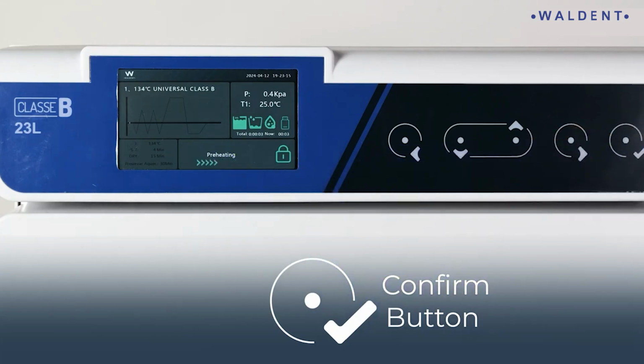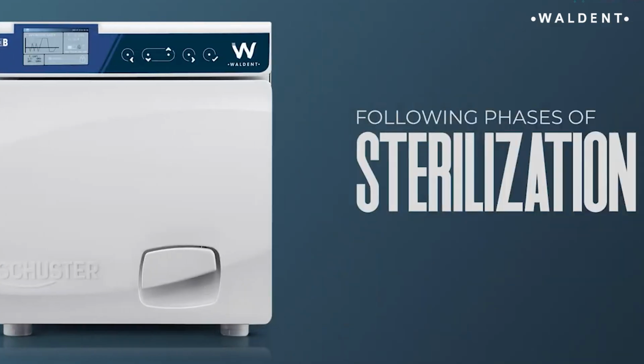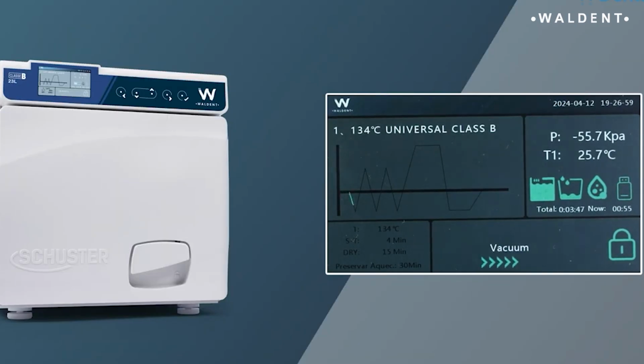Similarly, different cycles have different sterilization times. There are following phases of sterilization: preheating followed by vacuum, then heating, second time vacuum, again heating, third final time vacuum, final heating, sterilization, exhausting, drying, and balance or return period.